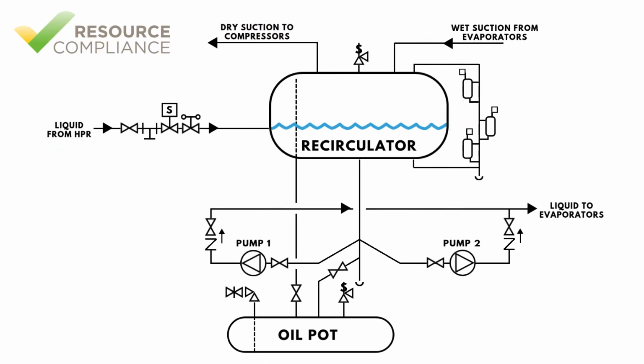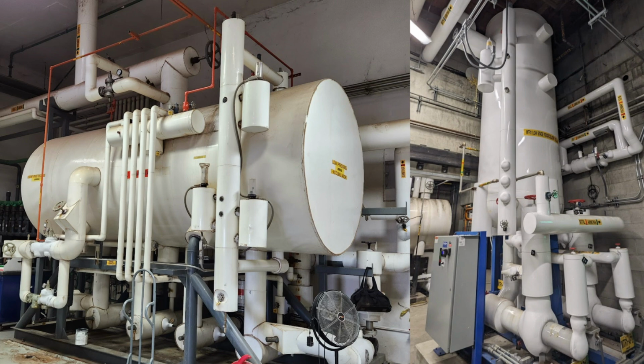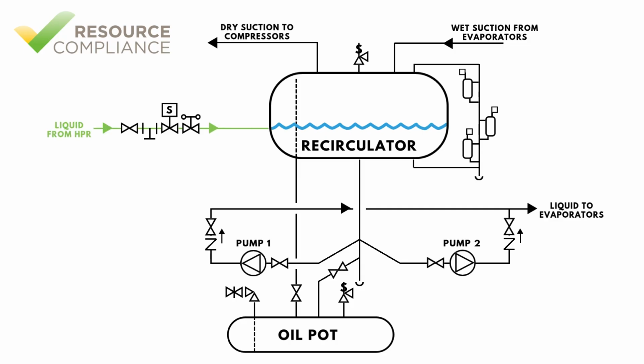A recirculator is typically part of a package consisting of a large recirculator vessel, an oil pot, and one or more pumps. Recirculators can be designed for horizontal or vertical orientation. Most often, the recirculator receives liquid from a high-pressure receiver. Before entering the vessel, the liquid passes through an expansion device that lowers its temperature and pressure. It then supplies, by gravity, low-pressure liquid to the ammonia pumps mounted underneath the vessel. Liquid and vapor returned from the evaporators are separated inside the recirculator to allow only vapor to be piped to the suction inlet on the compressor.